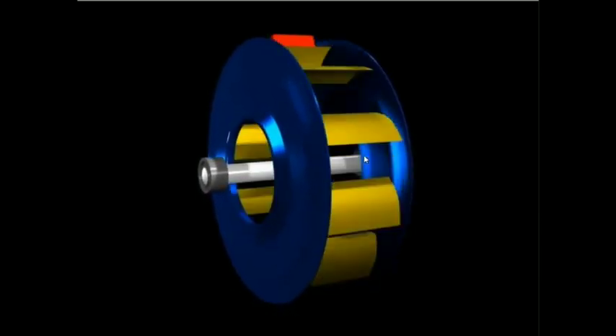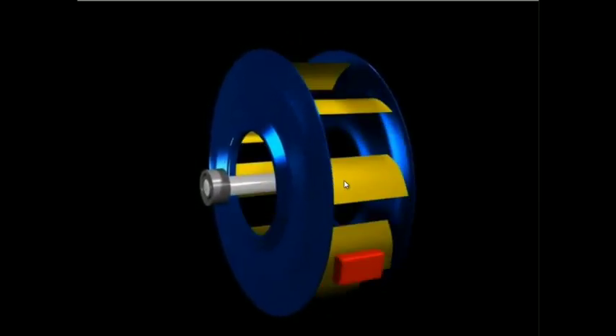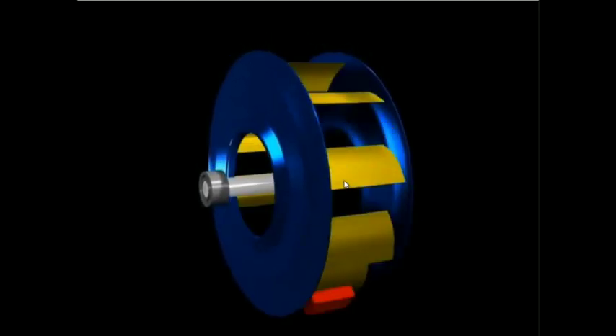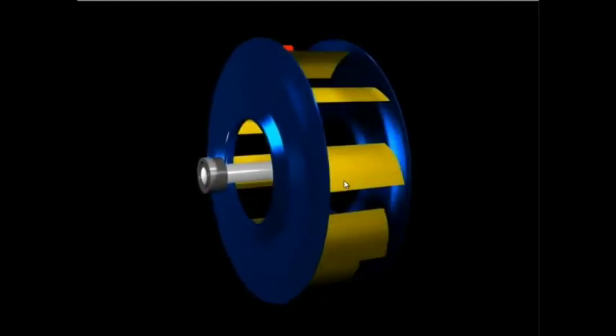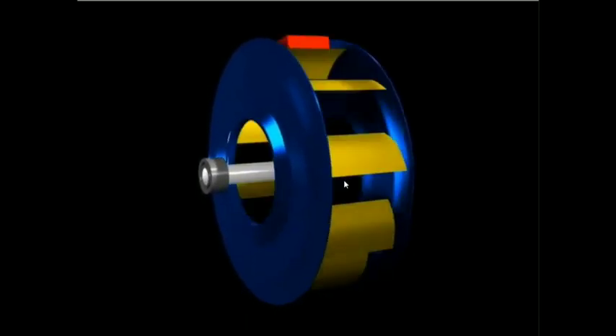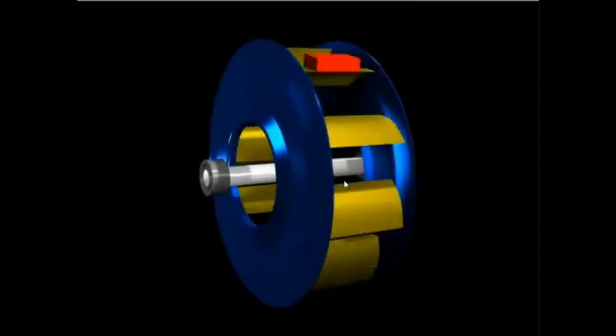Notice also in the case of static unbalance that the two ends of the rotor are moving up and down and from side to side in sync. So there's zero phase difference between the ends. Now it might not be exactly zero when you do this test, but it's close enough that you can say okay, it's static unbalance. And knowing that means you can do a single plane balance.